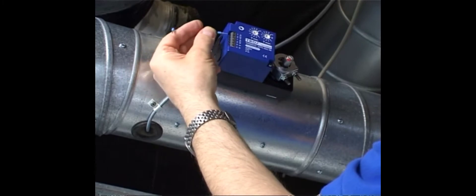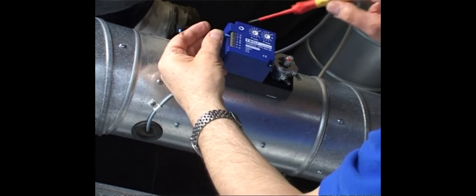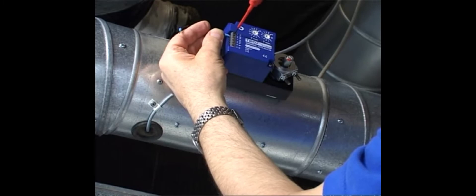By connecting the 24VAC to terminals 1 and 2, the actuator opens in anticlockwise direction.